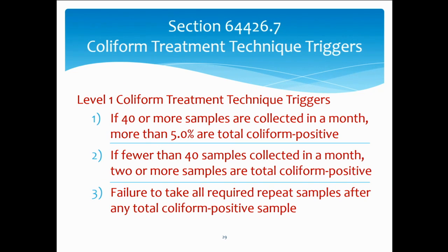So level 1 coliform treatment technique trigger. Do any of these conditions look familiar? They should, because the first 2 are the old TCR MCL violation. And then failure to take all required repeat samples after any total coliform positive sample. Remember, if you fail to take your repeat samples after an E. coli positive sample, that's an MCL violation. But if you fail to take your repeat samples after just a total coliform positive sample, you've exceeded level 1 treatment trigger, and you have to do a level 1 assessment, which we'll talk about.